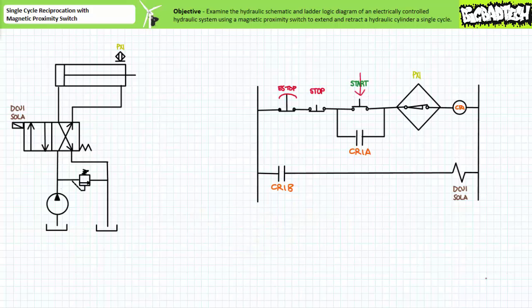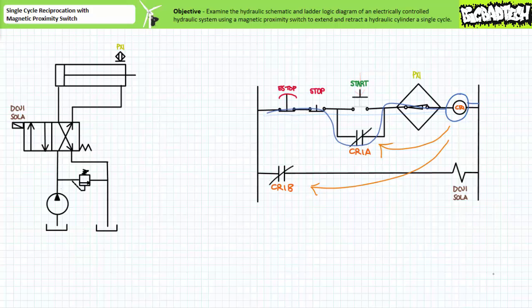Let's start by virtually pressing the start button on our ladder logic diagram. Given the e-stop, stop, and PX1 are all normally closed, we have a complete path of current — the coil of control relay CR1 energizes. All the contacts associated with CR1 change to their opposite state. CR1A and CR1B both close. With the holding contact CR1A closed, an operator can now release the momentary start push button. The start button returns to its normally open state, however we still have a complete current path through the holding contact to keep CR1 energized. That's the point of the holding contact — it maintains the last asserted state.